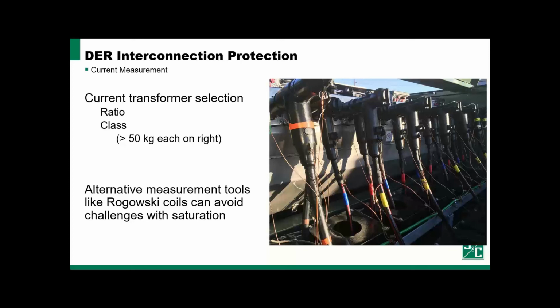Current transformers are the most common tool we use to measure current. To select them appropriately for a microgrid application, we first typically look at the ratio, and we try to identify a current transformer ratio that will enable our protective relays to detect the lowest levels of fault currents that we are facing or expecting in this system. Now, the challenge that goes with that is if we reduce the ratio, our current transformers can be driven into saturation with the high grid supplied fault current levels. And the current transformers are a static resource. They're not going to change when we change between grid tied and islanded mode. So we need to select them to work across both.